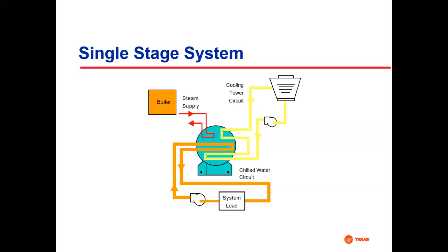That's a closed loop. And that really helps, because you don't have to do water treatment much on a chill water loop. When you fill it, the water has oxygen. But that little bit of oxygen is just a one-time deal. That oxygen causes a small amount of corrosion on the inside of the pipes. But then that's it. Once the oxygen is gone, that little bit of corrosion doesn't cause you a big issue. You just live with that. And that same water circulates around. It ought to stay pretty good. They probably put a little bit of treatment in.